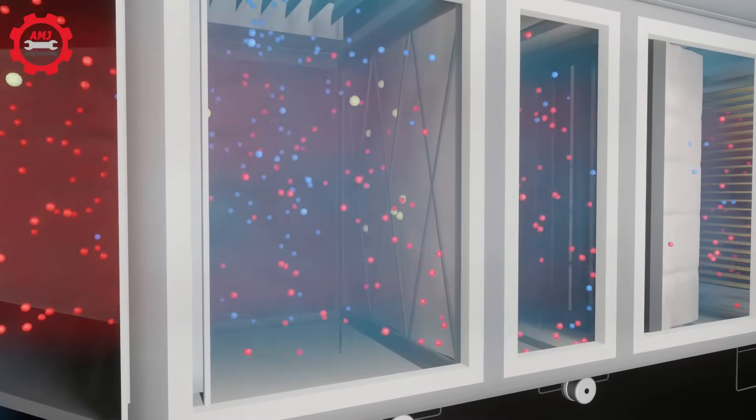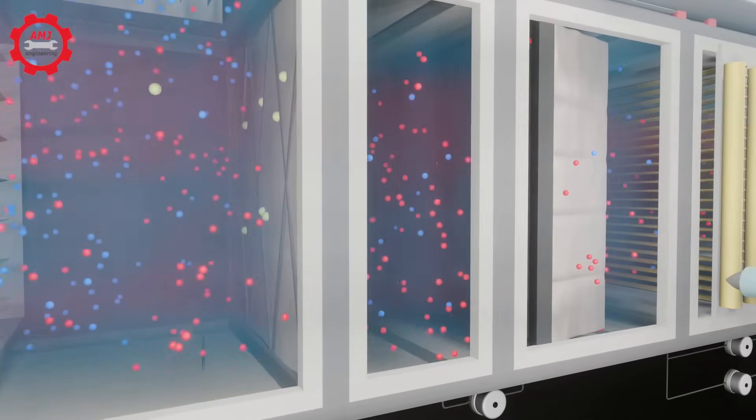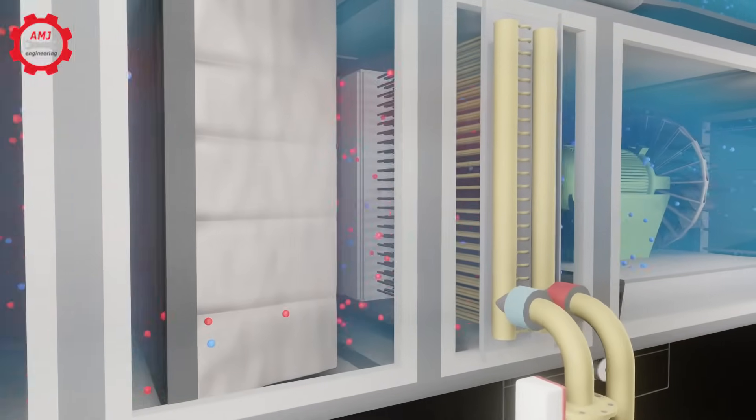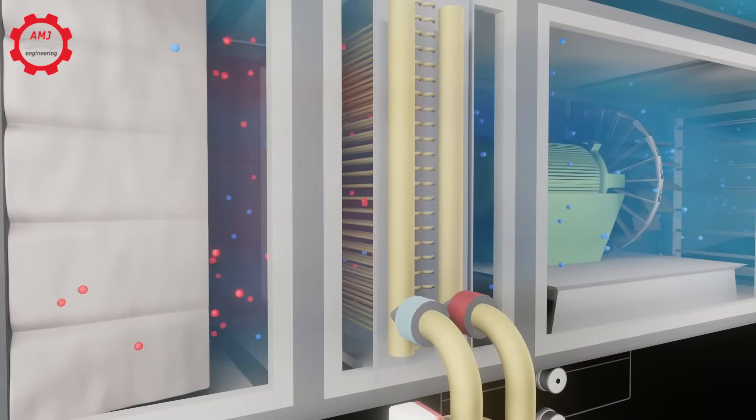It is common for an air handler to include a pre-filter and final filter setup, where a less efficient air filter is used to clean the air before it passes through a high-efficiency final filter.